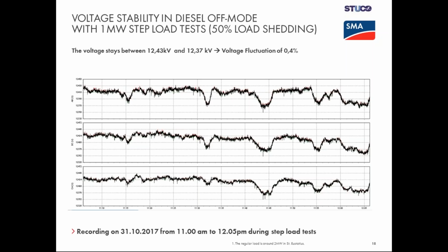And this is a zoom in on the voltage. I cannot tell you in this graph, and I really do not remember, when in time this was. It's 1 hour, and you can't see it. We had some other measurement equipment which should have registered the spike, but it actually did not register any spike. The voltage fluctuation is 0.4% during that hour.